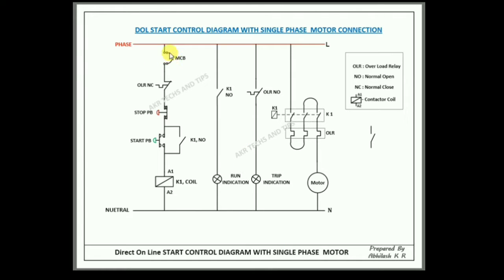When the MCB is closed, then the OLR normally closed point, then the stop button — this is also closed. When you press the start push button, the contactor coil will act and the contactor normally open contact will also close. That is how it works. You can push this button and close the normally open contact.